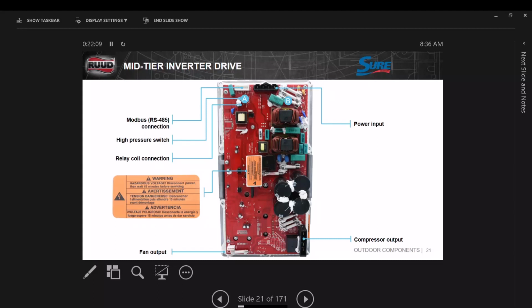So this board is going to send a PWM signal out to the motor so the motor can run at whatever speed this board needs it to be. It will always be engaged, so whenever the unit goes into high speed, in other words, goes up to third stage, the fan output still comes from the inverter, so it doesn't completely kill it. All it does is take the compressor out, switch the compressor over to the capacitor and contactor. And of course, here on the right, here's our compressor output. You'll have two outputs here, one going to the compressor from the inverter and one going to the compressor from the contactor.